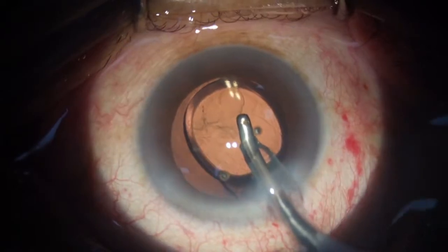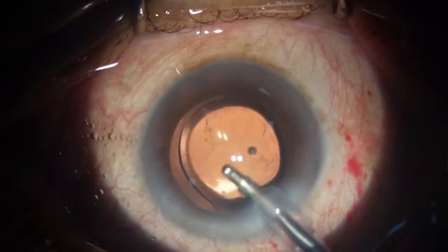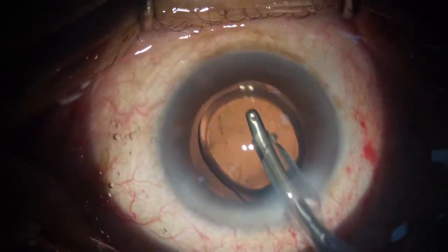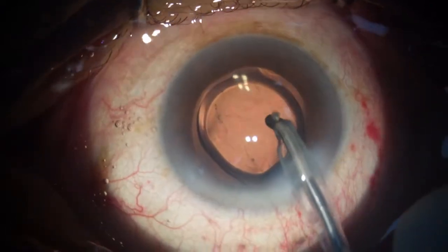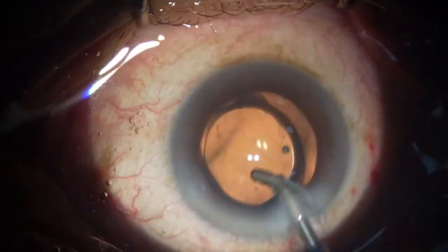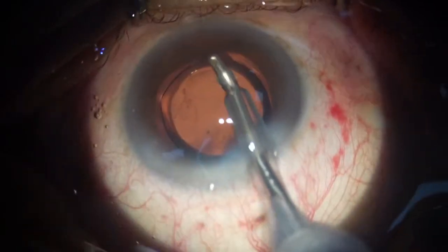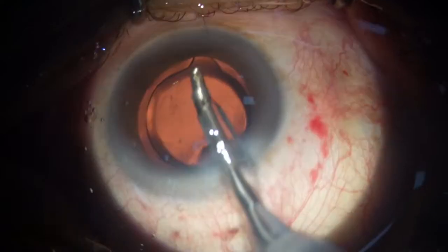So I get into the visco mode of the machine, and I have increased my vacuum to 650. That's the maximum that can go up.